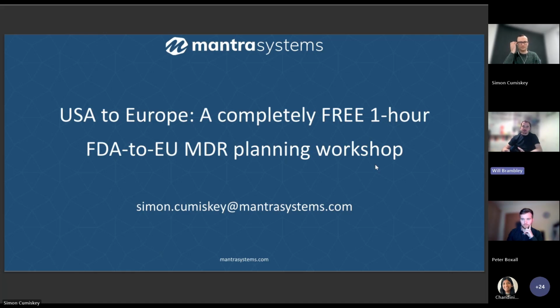Because as those things get more complex and the risk profile gets larger, the costs go up. The notified bodies will be operating with a higher level of scrutiny. And the other thing to factor in is rounds of review. If the notified body looks at your initial technical file and they identify problems with your equivalence claim, or with the clinical data you've used, or with some of your preclinical testing, those things can mean that you have to go through subsequent rounds of review, which add additional costs. So that's really why the range is so big, between 30,000 and 150,000.